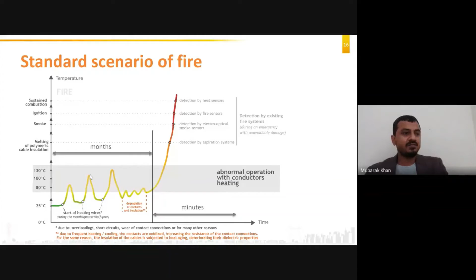Now, how can a loose connection convert to an arc flash? Okay, that is an important thing to understand. Under normal conditions, when the load is de-energized, the temperature of the joint will be something, suppose T degrees Celsius. When the load is switched on, the temperature will increase a little bit, so T plus delta T, for example. When the load is going to a full load, then the temperature of the joint will increase further.